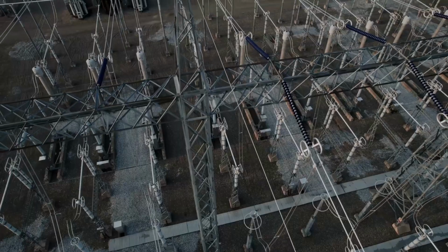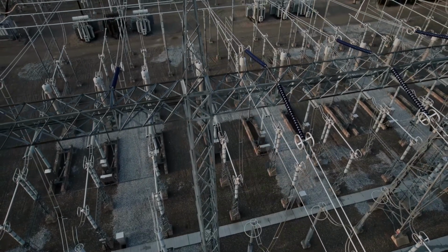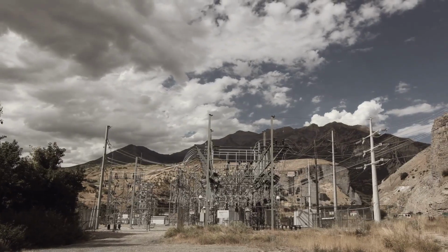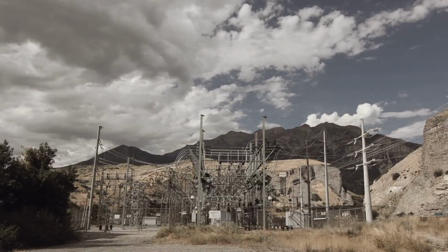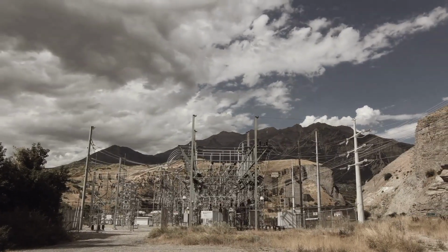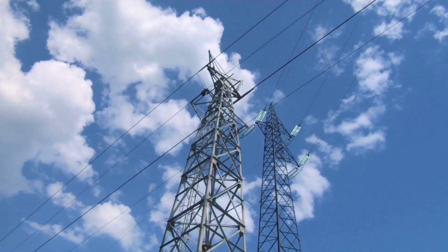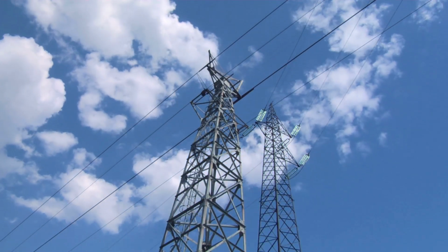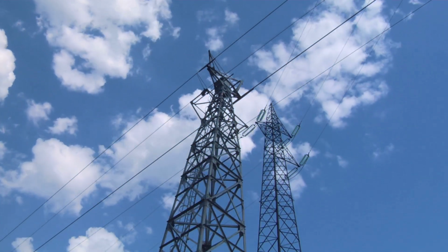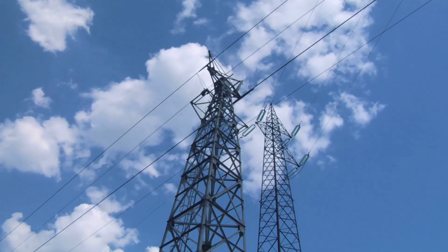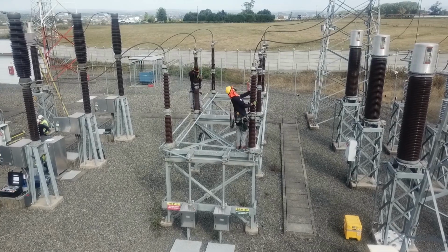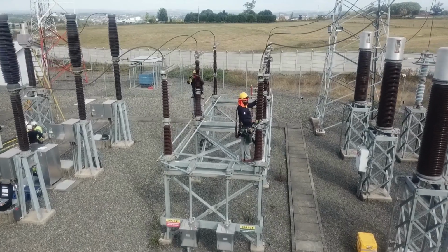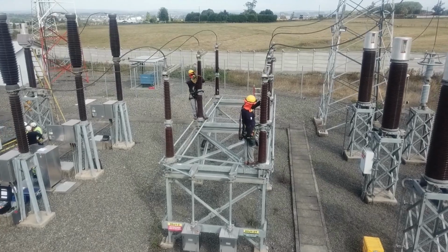Clause 4.5, Reconnection Protocols. Once a DER trips due to severe voltage or frequency excursions, it cannot instantly rejoin the grid. IEEE 1547 mandates a minimum 5-minute reconnection delay, or longer, based on utility protocols. This allows grid voltage and frequency to settle, and prevents the chaos of hundreds of DERs coming online simultaneously. From the FRT lens, the DER must wait, monitor, and synchronize before reconnecting, preventing cascading failures.